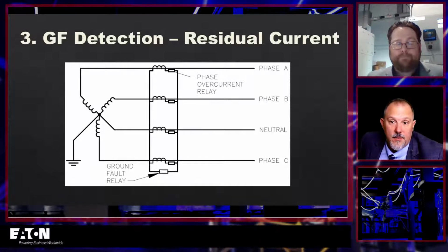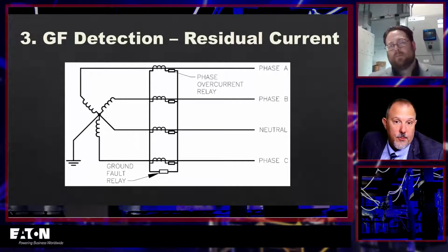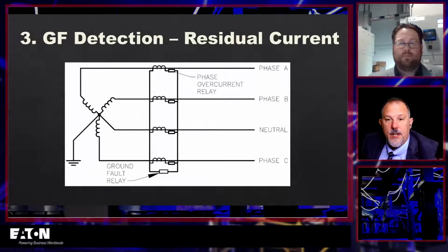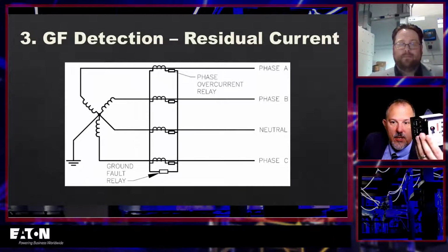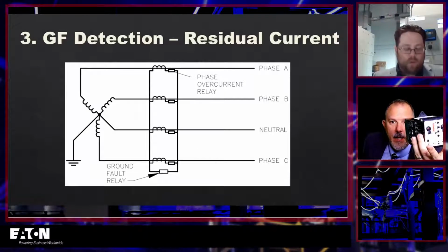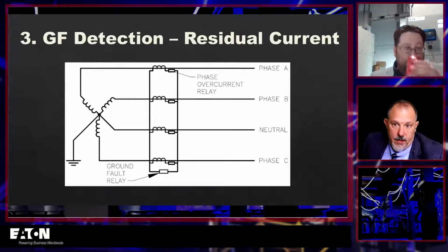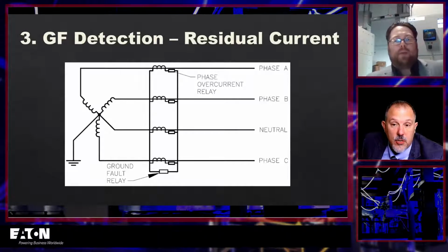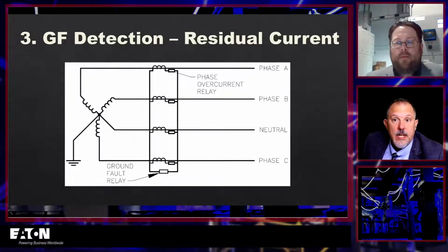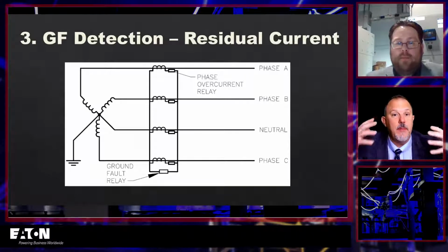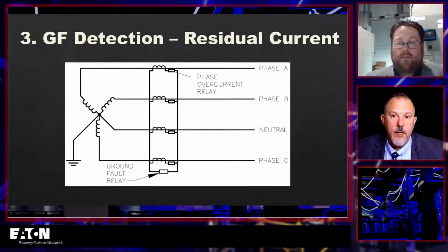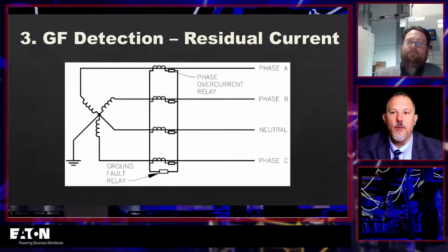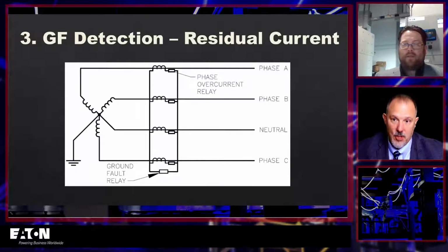Even if it was a circuit breaker, you're going to have to change the breaker out. In that case, you think about how we do this on fusible equipment. We use stuff like this, which is a relay, right? And this relay will shunt trip the switch. It doesn't tell the fuse to open. It basically tells the switch to open, but your switch has to be mechanically able to open based upon a control voltage or some sort of control. If your switch itself isn't able to do that, then it complicates the situation.